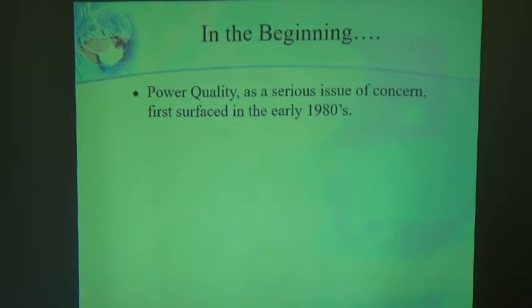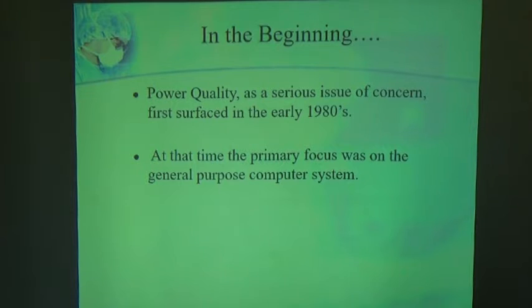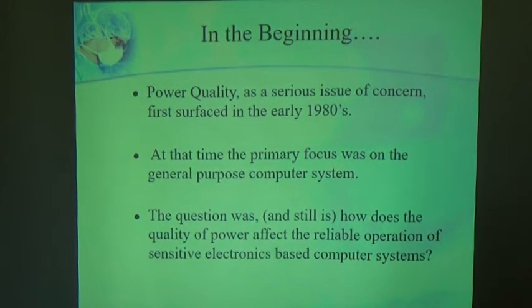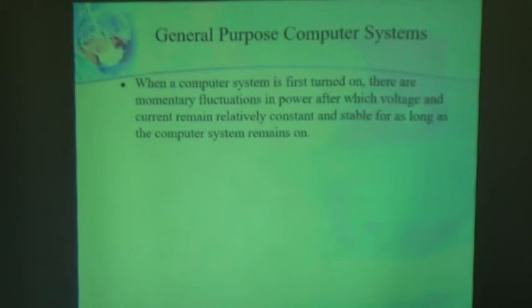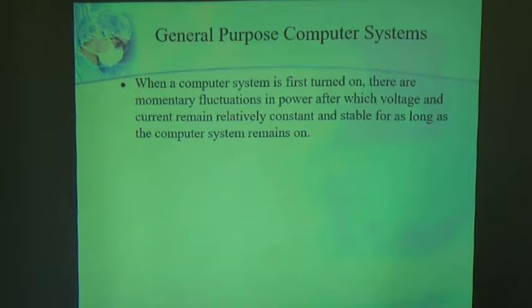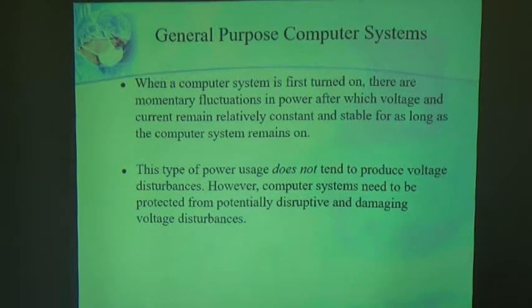Power quality is a serious issue of concern first surfaced in the early 1980s. At that time, the primary focus was on the general purpose computer system. The question was, and still is, how does the quality of power affect the reliable operation of sensitive electronics-based computer systems? When a computer system is first turned on, there are momentary fluctuations in power, after which voltage and current remain relatively constant and stable for as long as the computer system remains on. This type of power usage does not tend to produce voltage disturbances. However, computer systems need to be protected from potentially disruptive and damaging voltage disturbances.